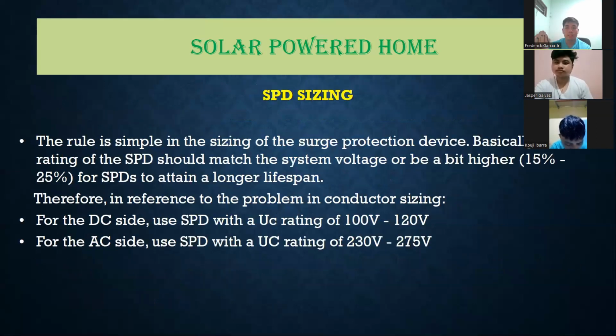Now we have the SPD sizing. The rule is simple in sizing of the surge protection device. Basically, the UC rating of the SPD should match the system voltage, or of course be a bit higher, around 15% to 25%, for SPDs to attain longer lifespan. Therefore, in reference to the problem in conductor sizing, for the DC side, use an SPD with a UC rating of 100 to 120 volts. For the AC side, use an SPD with a UC rating of 230 to 275 volts.